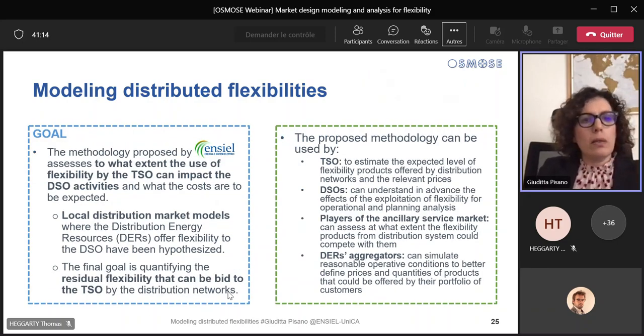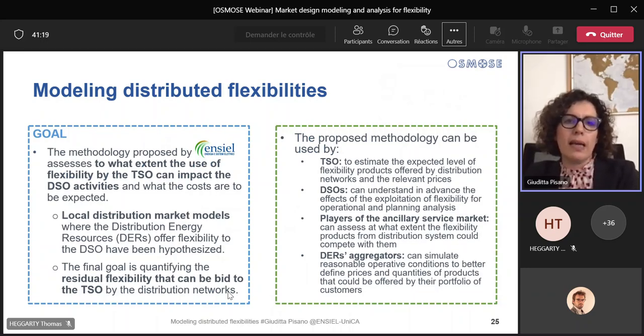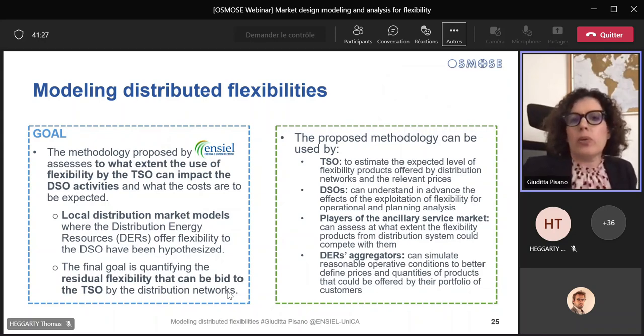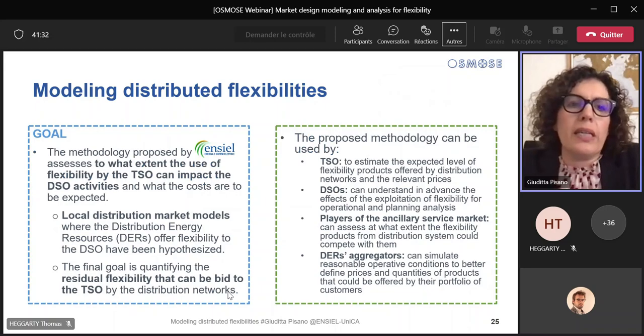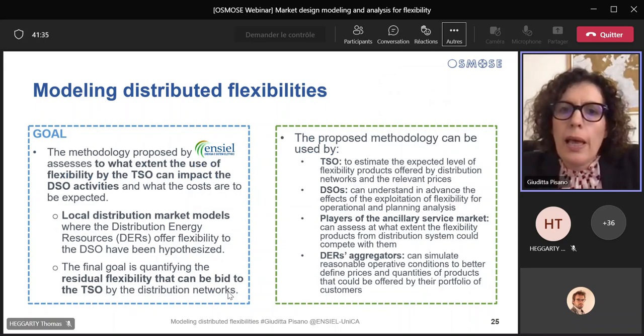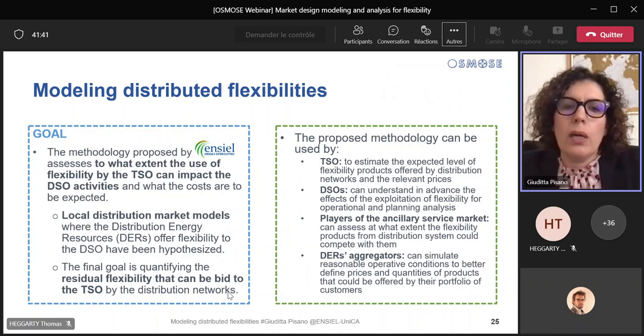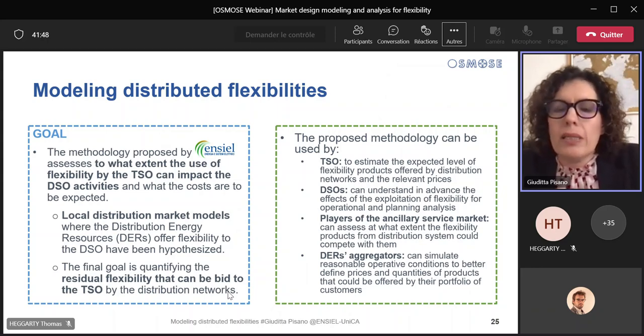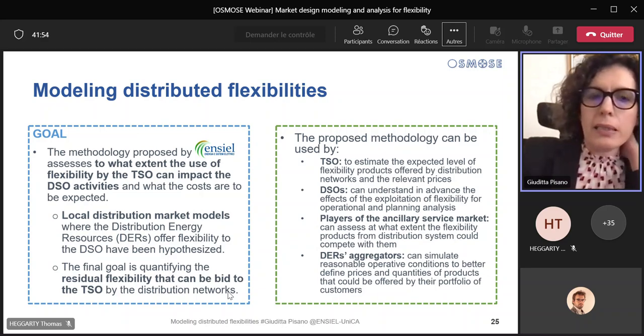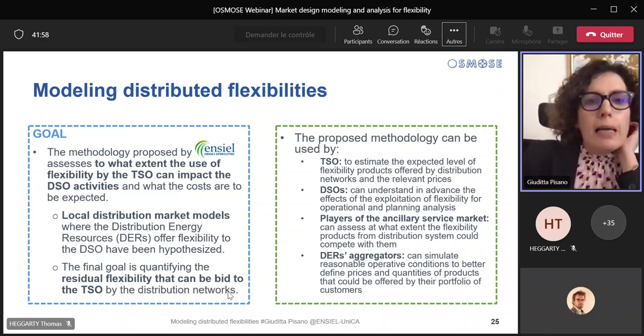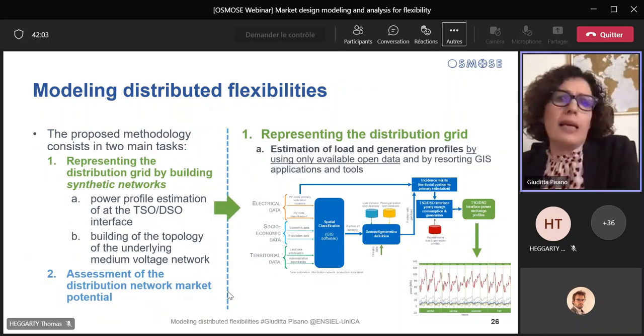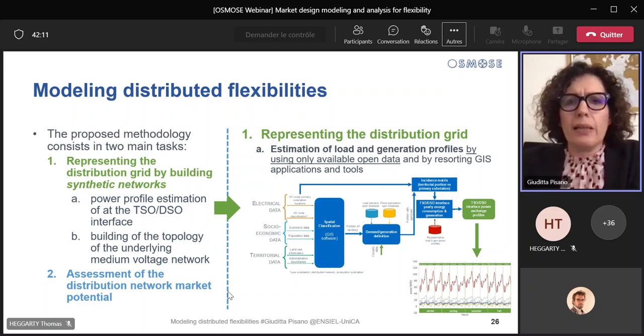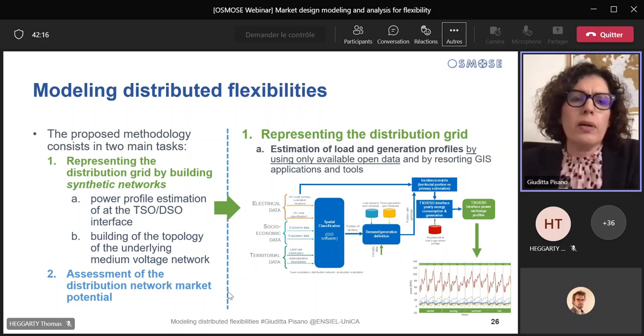The final goal of our methodology is to assess to what extent the use of flexibility by the TSO can impact DSO activities. We hypothesized local market models where DSO can exploit a quota of flexibility from the DERs to solve internal operational issues. And we quantified the residual flexibility that can be offered to the TSO in the global ancillary service market by the same resources. Such an approach can be used by all the stakeholders of the power system from different points of view. The proposed methodology consists of two main tasks. We firstly estimated the load and generation profiles at the TSO-DSO interfaces by using open data only and GIS application and tools.